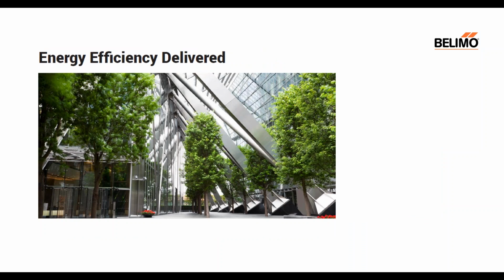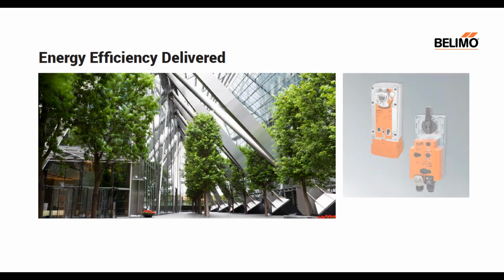Smart control of heating, cooling, and ventilation loads have a big impact on energy efficiency of buildings. Belimo damper actuators consume up to 80% less energy than others do. This is because of our patented brushless DC motor technology equipped with dynamic holding force detection. The motor technology guarantees rated torque over the entire operating range with no loss in performance due to temperature, supply voltage, or speed.